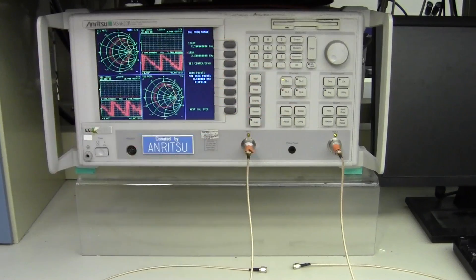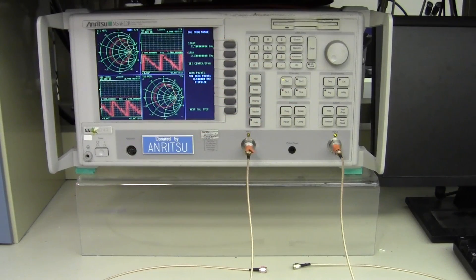On the number pad on the right, it has order of magnitude buttons for gigahertz, megahertz, and kilohertz. You do need to be careful that as you're typing them in, you never have your stop frequency be lower than your start frequency because the vector network analyzer will complain.